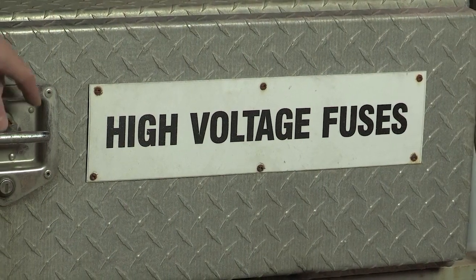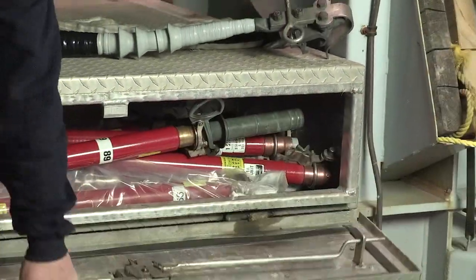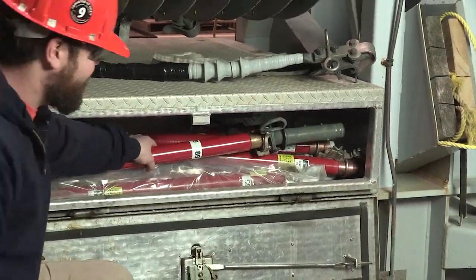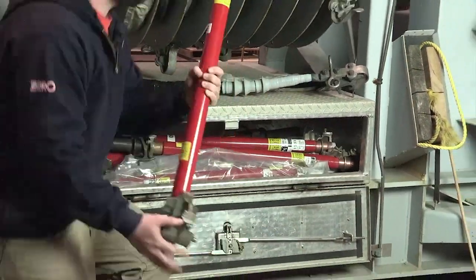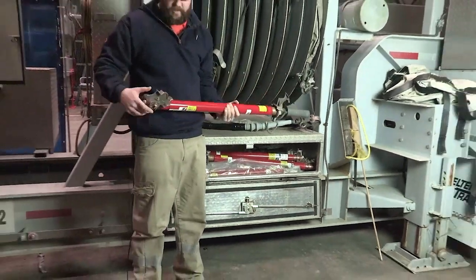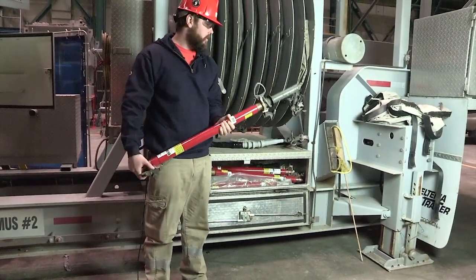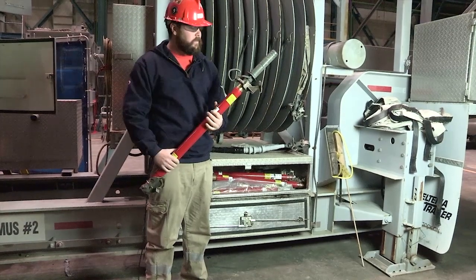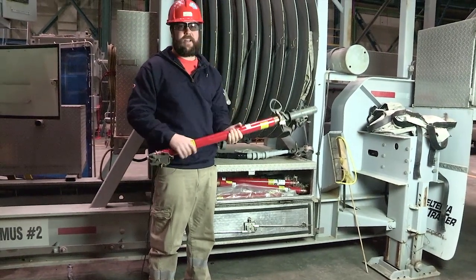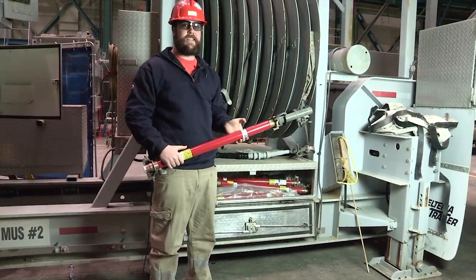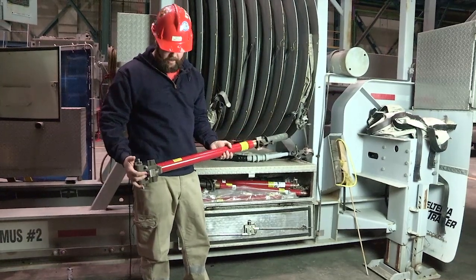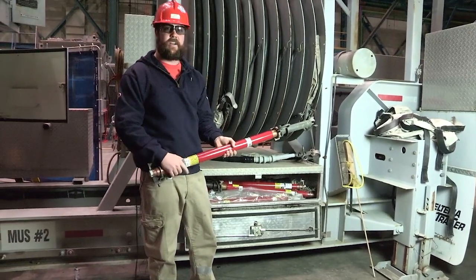Up next, we've got the high voltage fuses compartment. You want to open that up and inspect the fuses that are dressed. You want to just make sure they're cleaned, everything operates and is oiled. You want to also make sure that every fuse that is carried on the MUS is blow tested or airflow tested, and you want to put a new inspection date sticker on them.